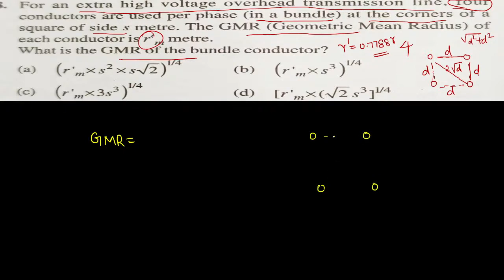Now, what is the GMR of the bundled conductor? That is a very simple question. Let us solve. How will you calculate the geometric mean radius? Totally how many conductors are there? 4 conductors are there: conductor 1, conductor 2, conductor 3, conductor 4. So you have to calculate 4 times in order to get the GMR, calculating for each conductor's point of view.